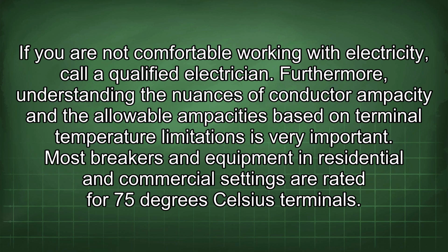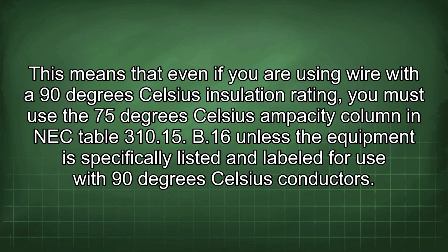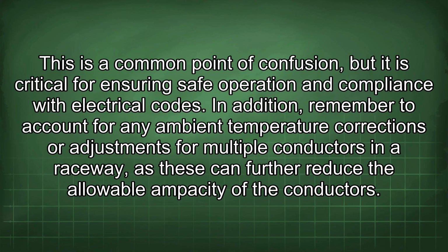Furthermore, understanding the nuances of conductor ampacity and the allowable ampacities based on terminal temperature limitations is very important. Most breakers and equipment in residential and commercial settings are rated for 75 degrees Celsius terminals. This means that even if you are using wire with a 90 degrees Celsius insulation rating, you must use the 75 degrees Celsius ampacity column in NEC Table 310.15(B)(16) unless the equipment is specifically listed and labeled for use with 90 degrees Celsius conductors. This is a common point of confusion, but it is critical for ensuring safe operation and compliance with electrical codes.